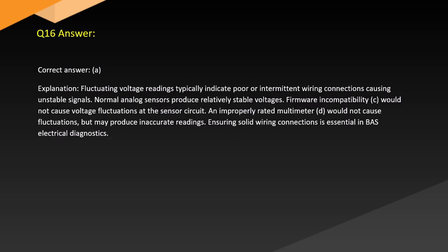Answer. Correct answer: A. Explanation. Fluctuating voltage readings typically indicate poor or intermittent wiring connections causing unstable signals. Normal analog sensors produce relatively stable voltages. Firmware incompatibility, C, would not cause voltage fluctuations at the sensor circuit. An improperly rated multimeter, D, would not cause fluctuations but may produce inaccurate readings. Ensuring solid wiring connections is key to BAS electrical diagnostics.